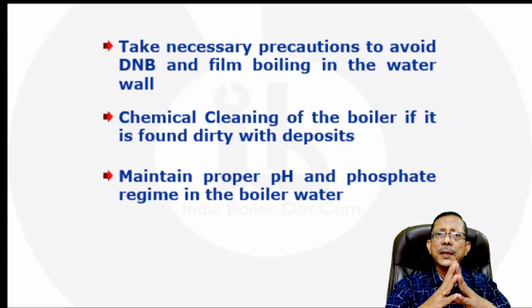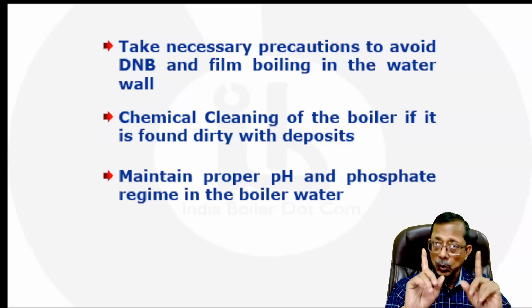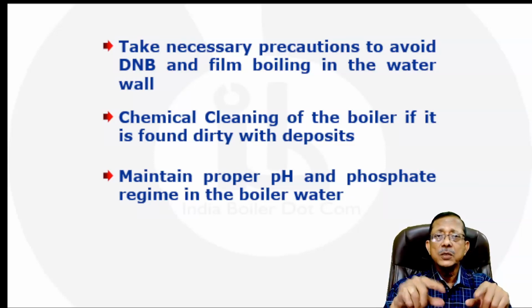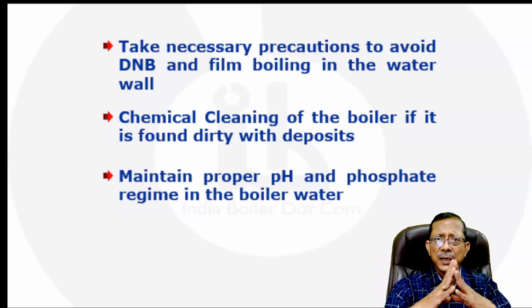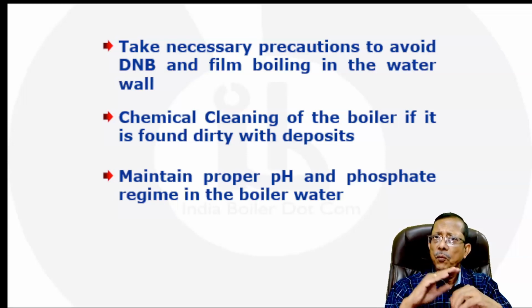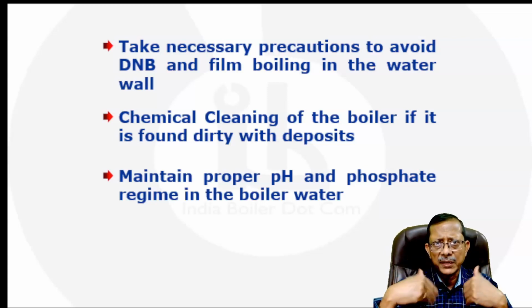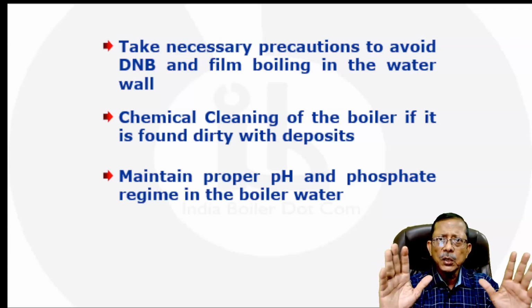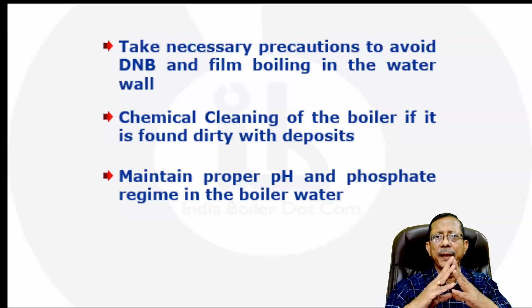For a high pressure boiler, 9.7, 9.8, though it is within the limit, because if you see the limit, it will be around 9.2 to 9.8 in the case of a 120 KSC boiler. In the case of a 150 plus KSC boiler, it will be around 9.2 to 9.6. Now the thing is that we have to limit the pH well within that, right? So 9.4 to 9.5, that is what I suggest. We should not go beyond that.